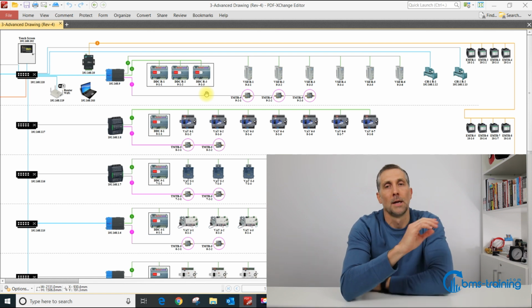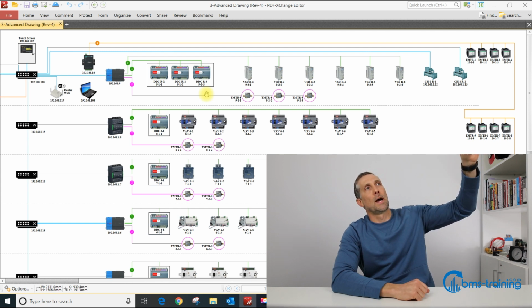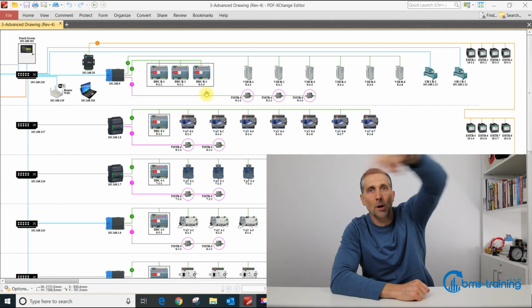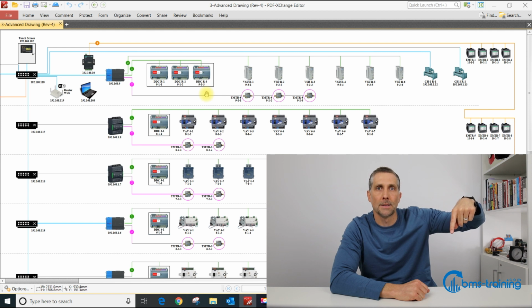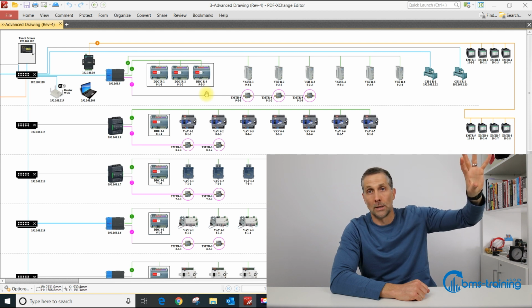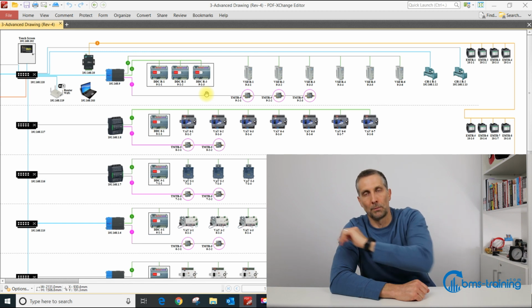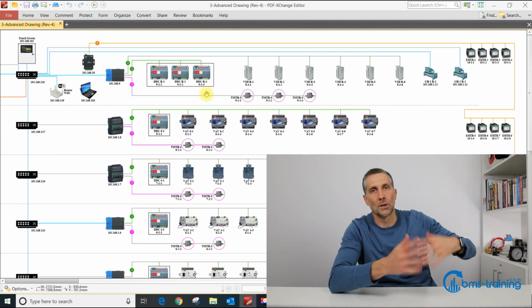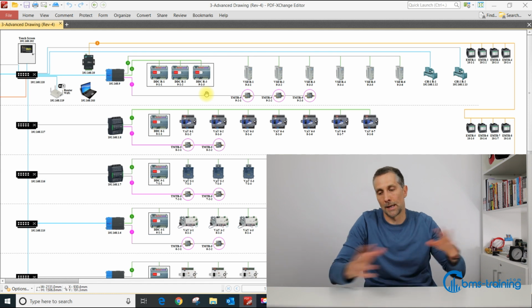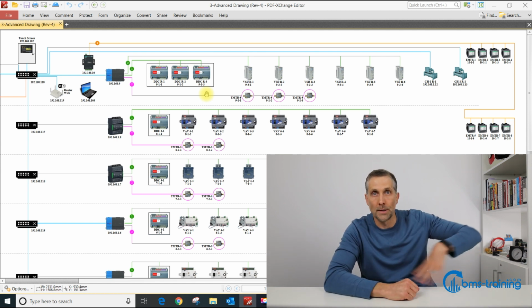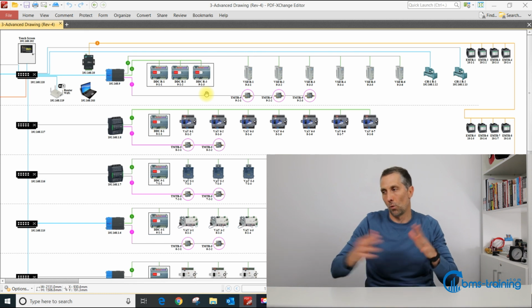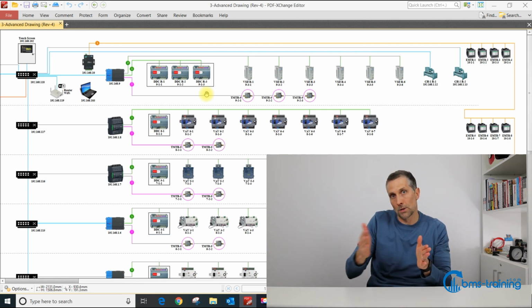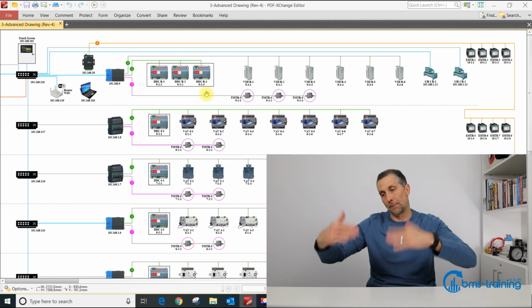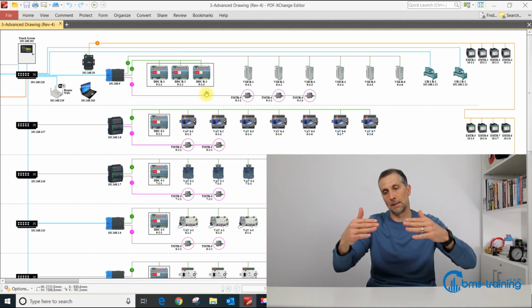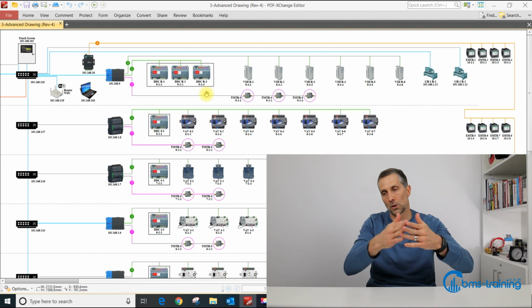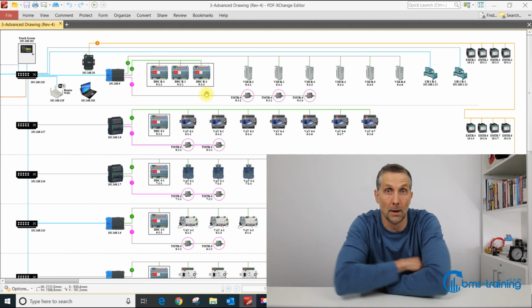And that's useful because the energy management system is now polling its own subnetwork, collecting the kilowatt hours every 15 minutes. If you have a lot of data going to variable speed drives, it's collecting from the variable speed drives. And if you have BMS activity, changing set points, starting and stopping of equipment, status checking and so on, that's all happening in its own subnetwork. So we're taking that long subnetwork with the master slave token passing and separating it into 3 subnetworks. So the token can now go 3 times on 3 different subnetworks.